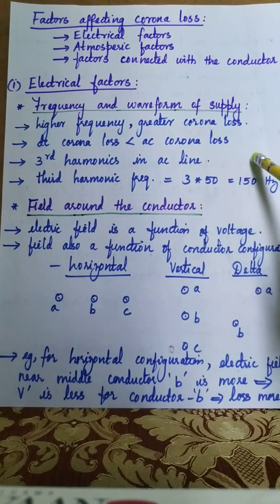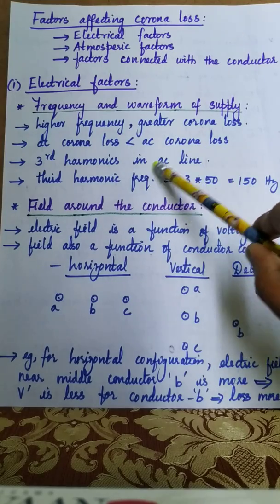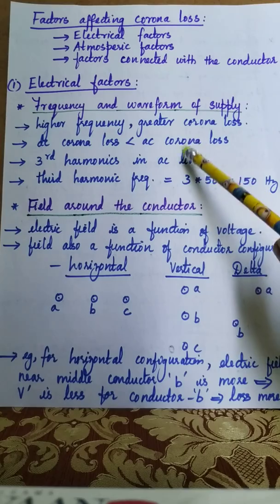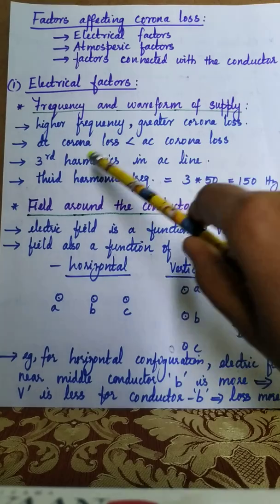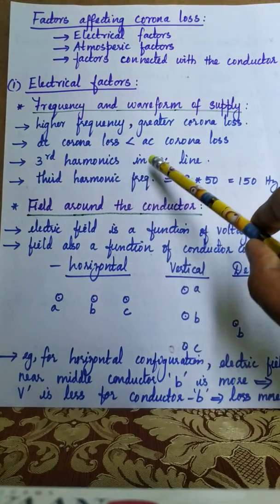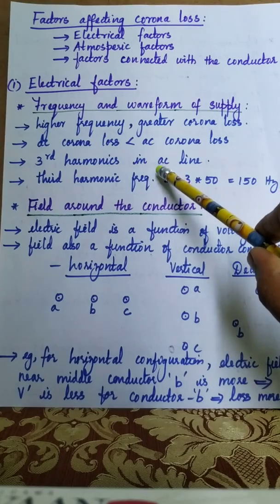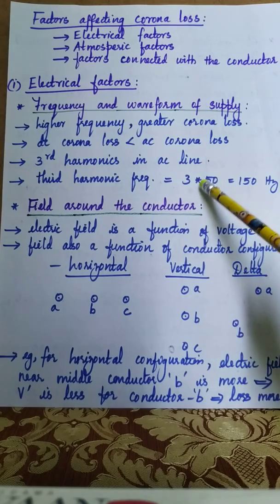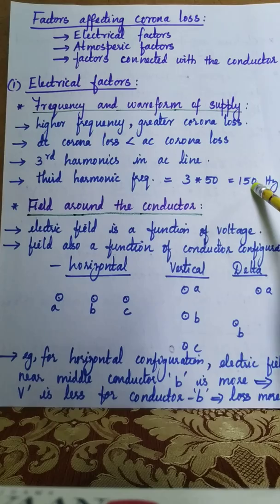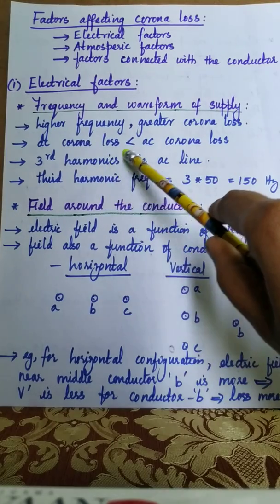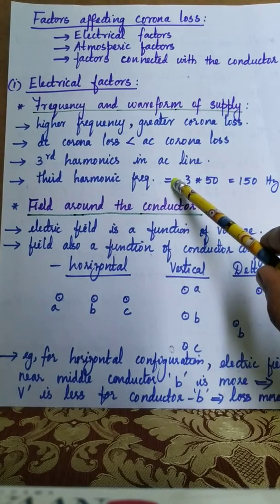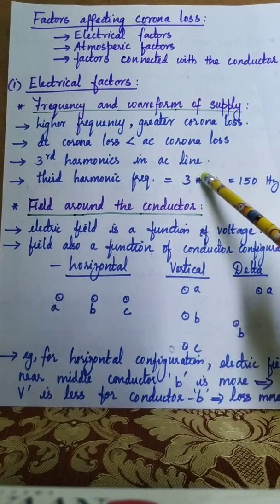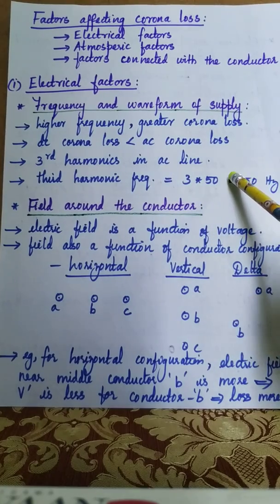Regarding the nature of the waveform: in an AC line, apart from the fundamental frequency of 50 Hz, third harmonic waveforms also exist. The frequency of the third harmonic component is 3 × 50 = 150 Hz. Due to the presence of third harmonics in the AC line, corona power loss will further increase because power loss is directly proportional to frequency.